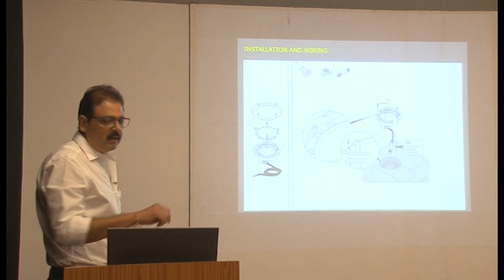With this, use the IP connectors, put the fitting into the housing, and we just have to screw it to the last level. Always tighten it in a cross condition, because most luminaires may have 4 screws to 8 screws. So always tighten in an opposite direction, and that's how you finally are ready for installation.